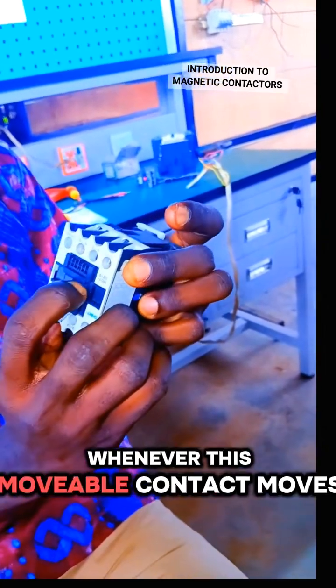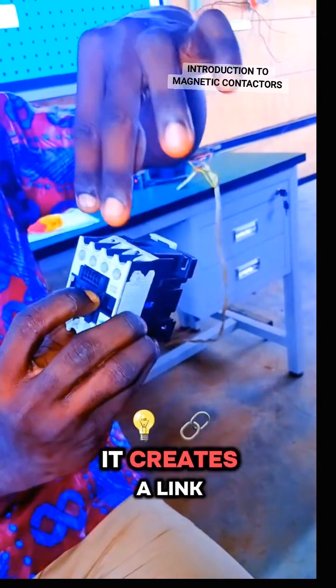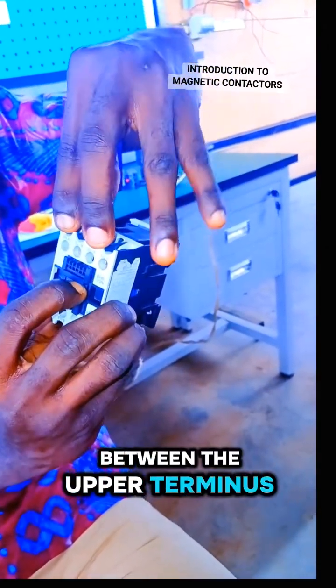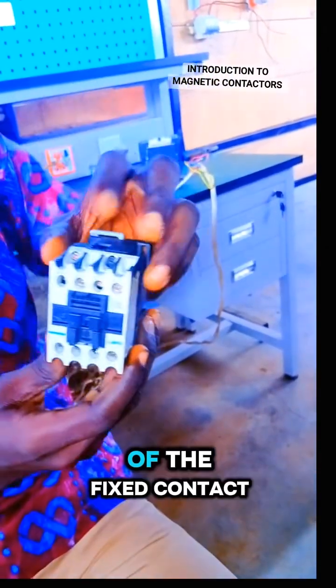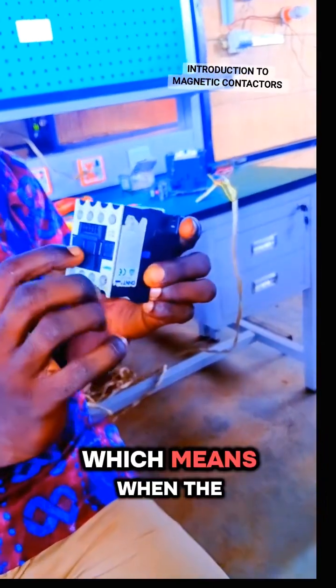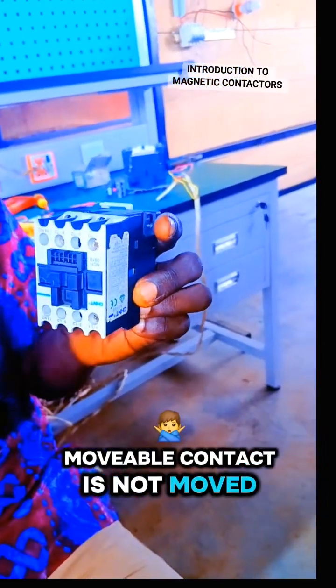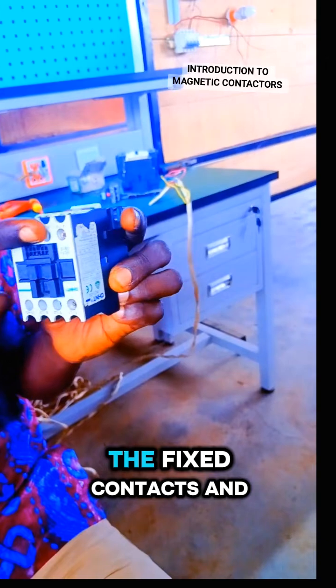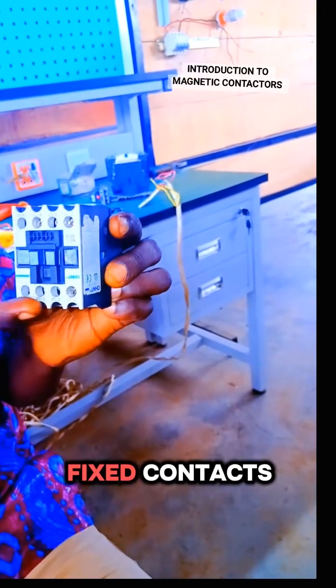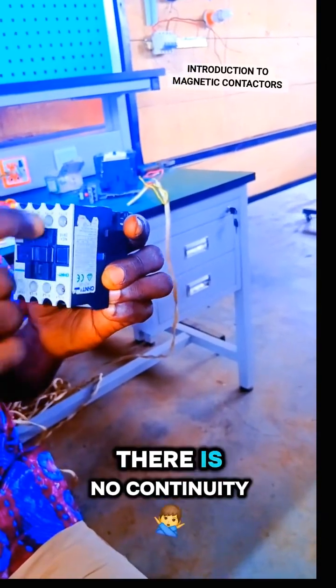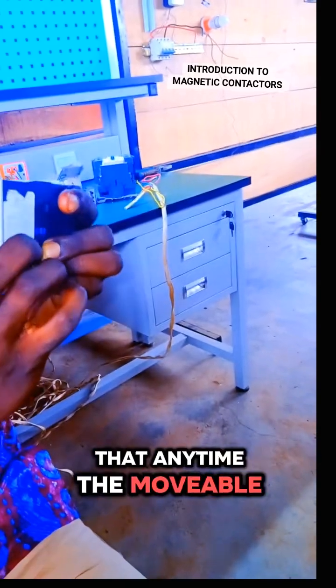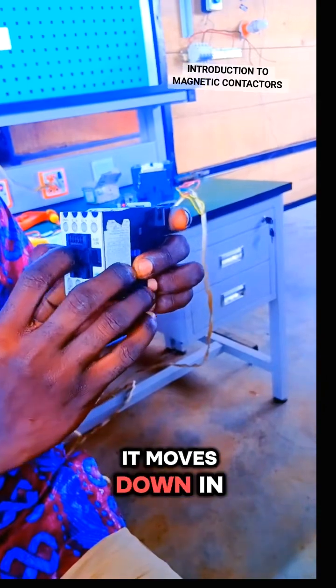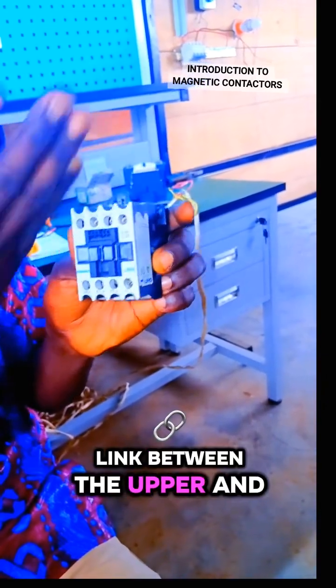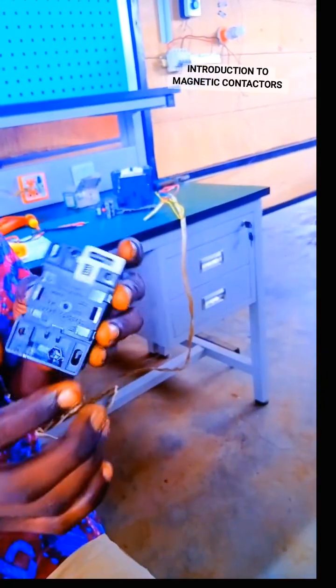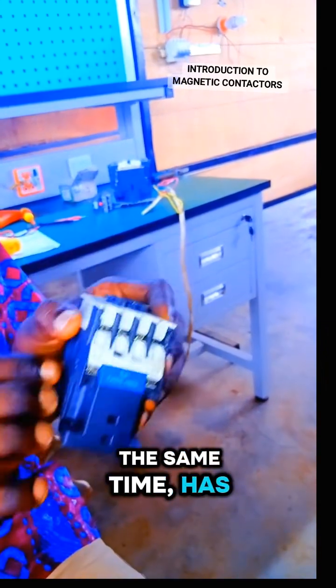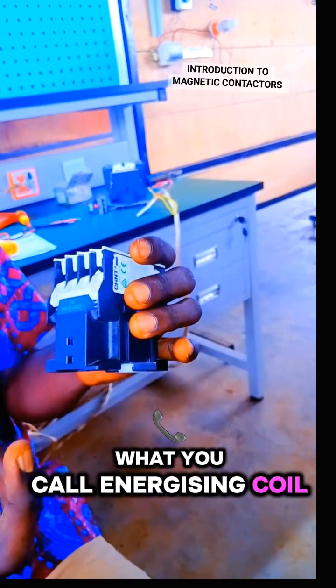Whenever this movable contact moves, it creates a link between the upper terminals and the lower terminals of the fixed contact. Which means when the movable contact is not moved, the upper terminal in the fixed contact and the lower terminal in the fixed contact are open. There is no continuity between them. But anytime the movable contact moves, it moves down in order to create a link between the upper and the lower terminal. The magnetic contactor at the same time has what we call an energizing coil.